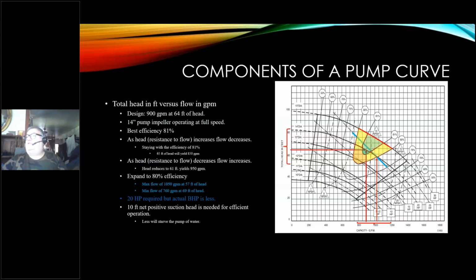Then I'll pick it at that resistance. I hope my system resistance does not exceed this, because then it will restrict my flow. So I better be operating somewhere in this. See how the actual resistance narrowed me down. This is where I can operate with this pump and maintain my flow, anything below that blue line as far as resistance goes. Max flow of 1050 GPM at 57 feet of head, and a minimum flow of 760 at 69 feet of head. So the higher resistance cuts down my flow.